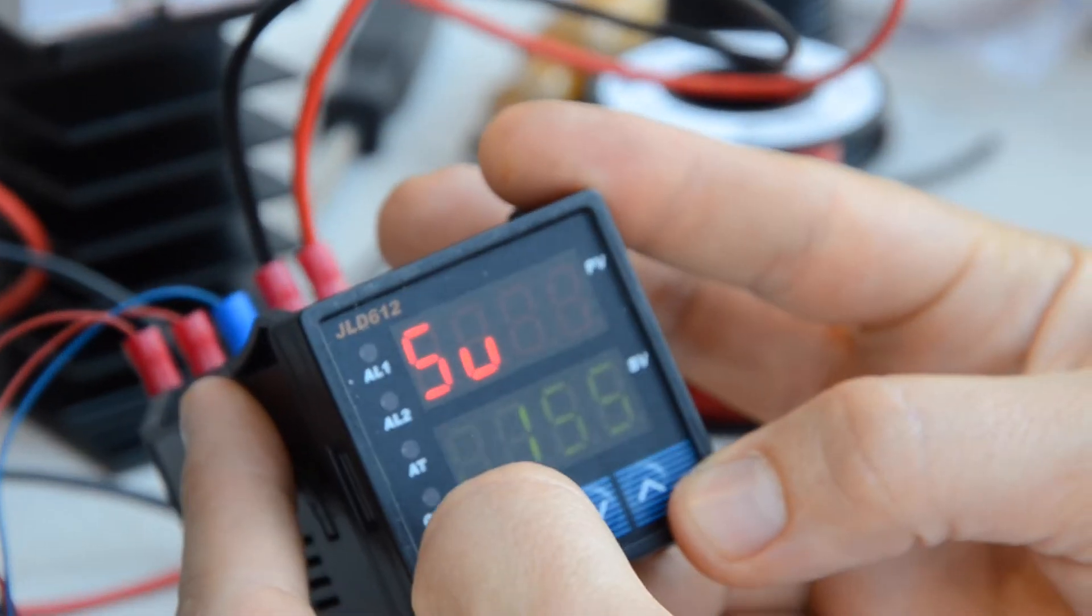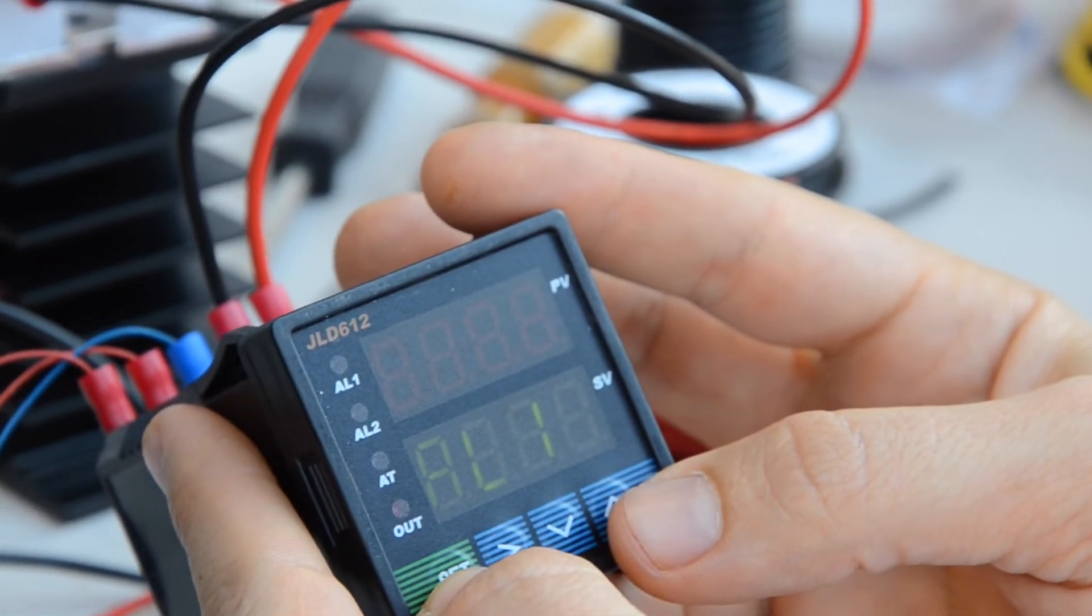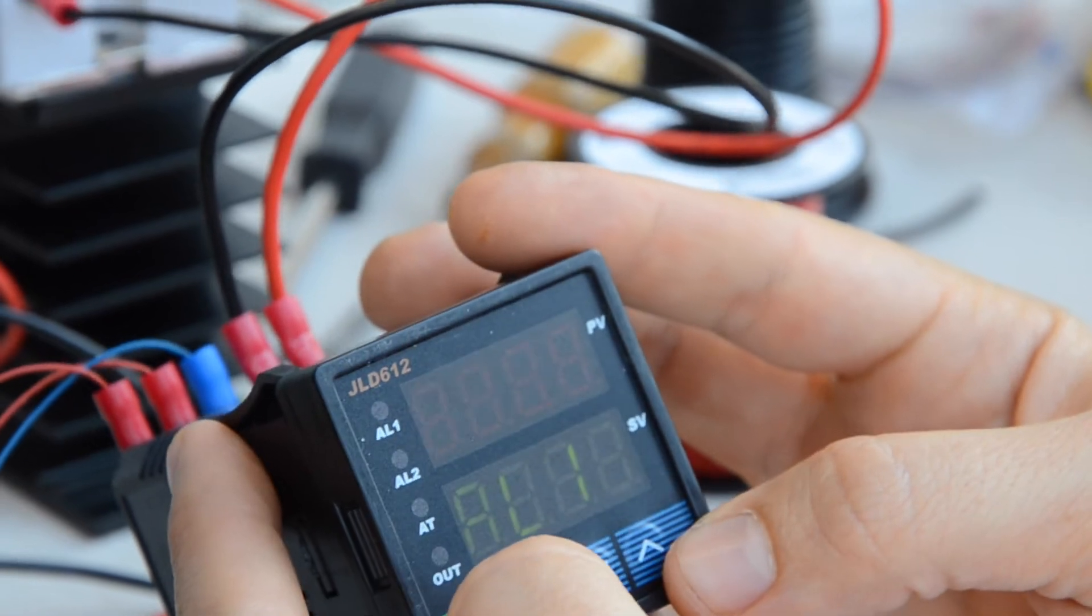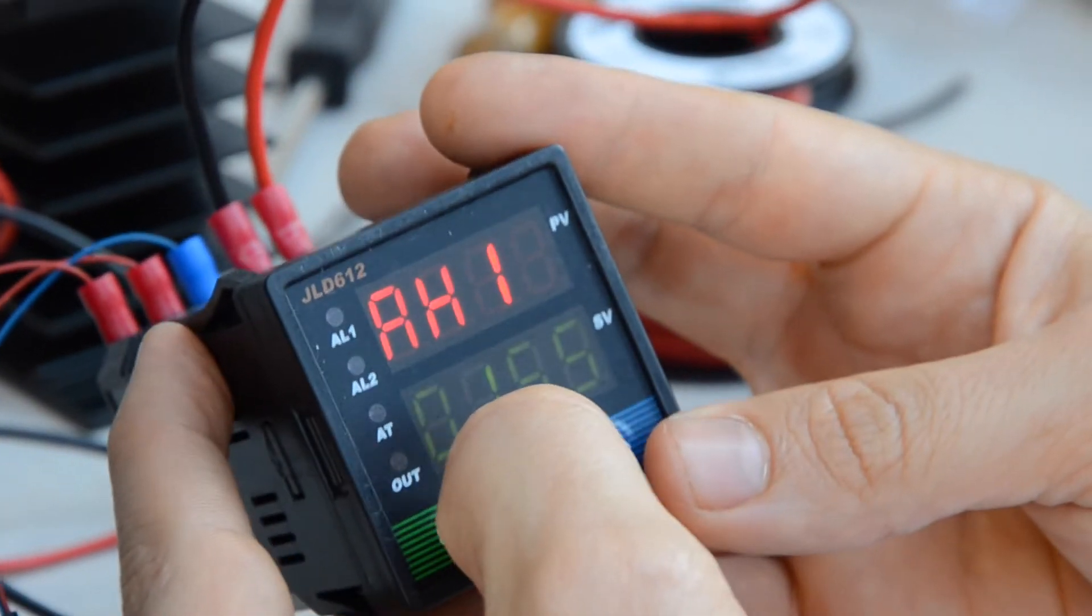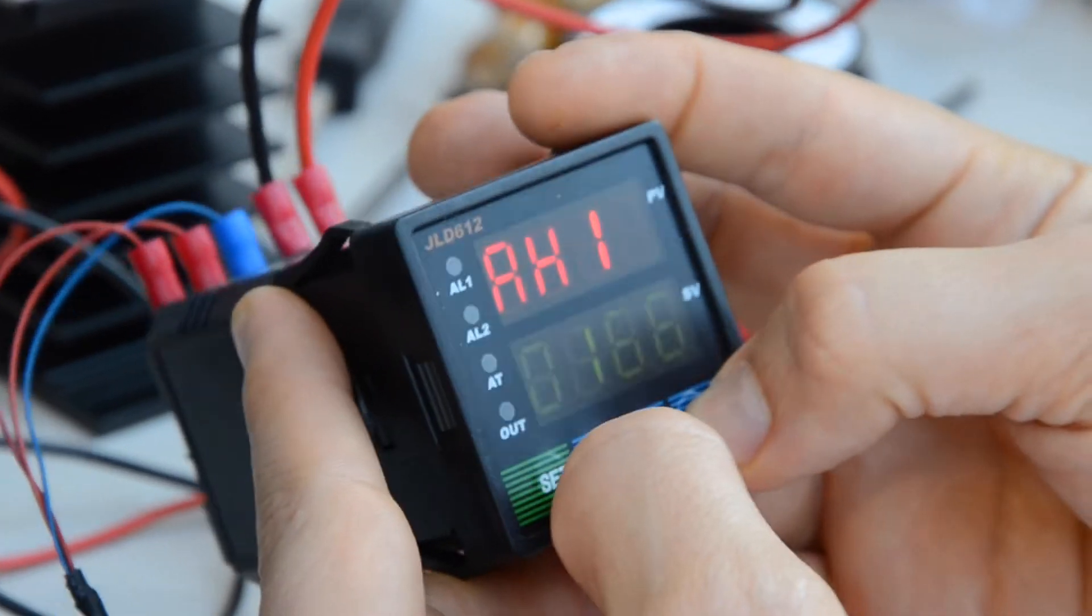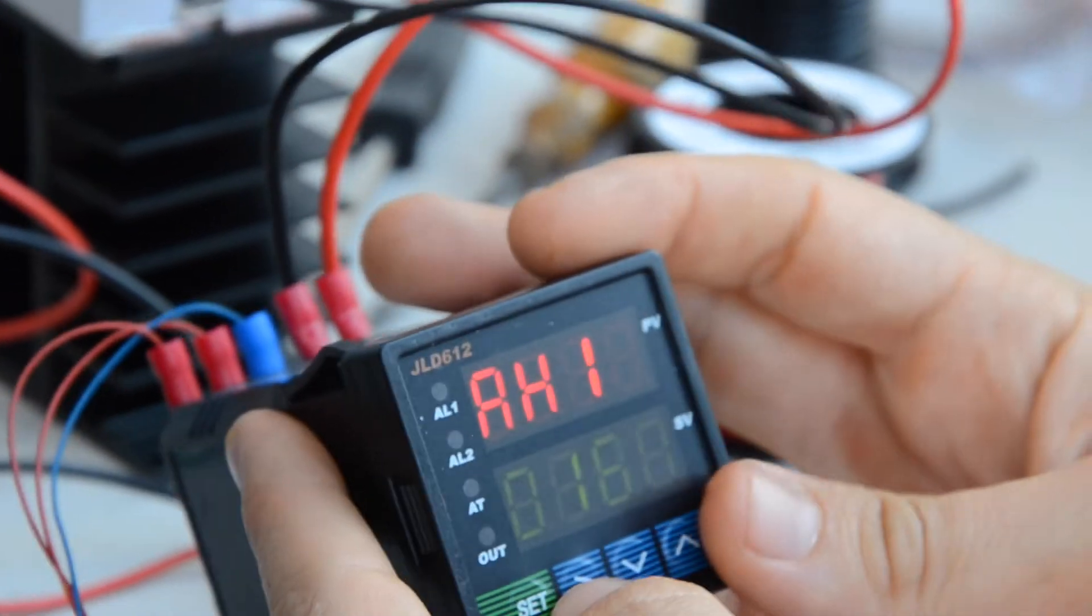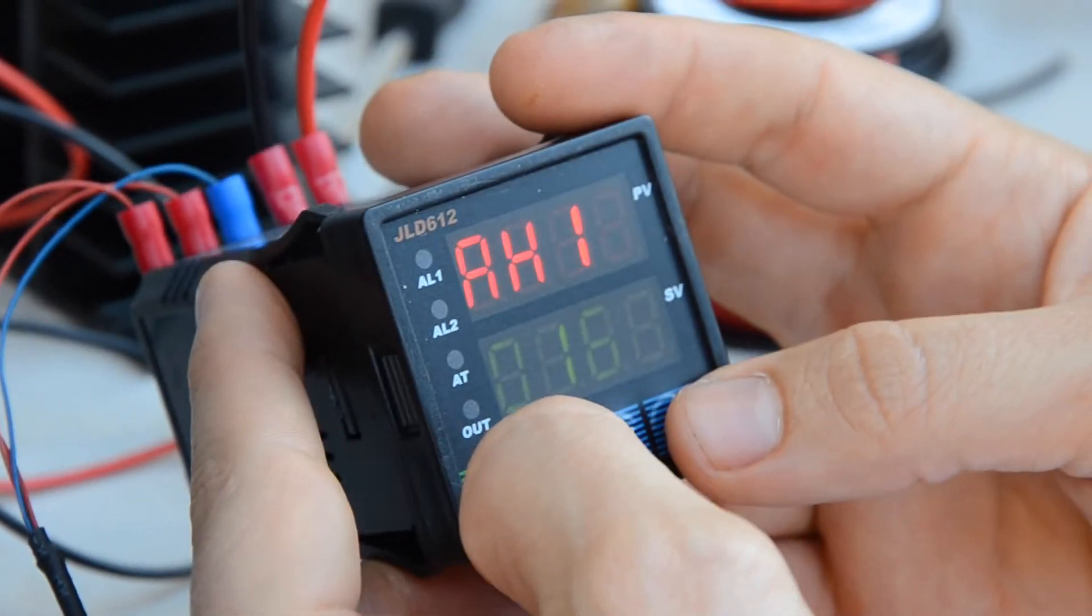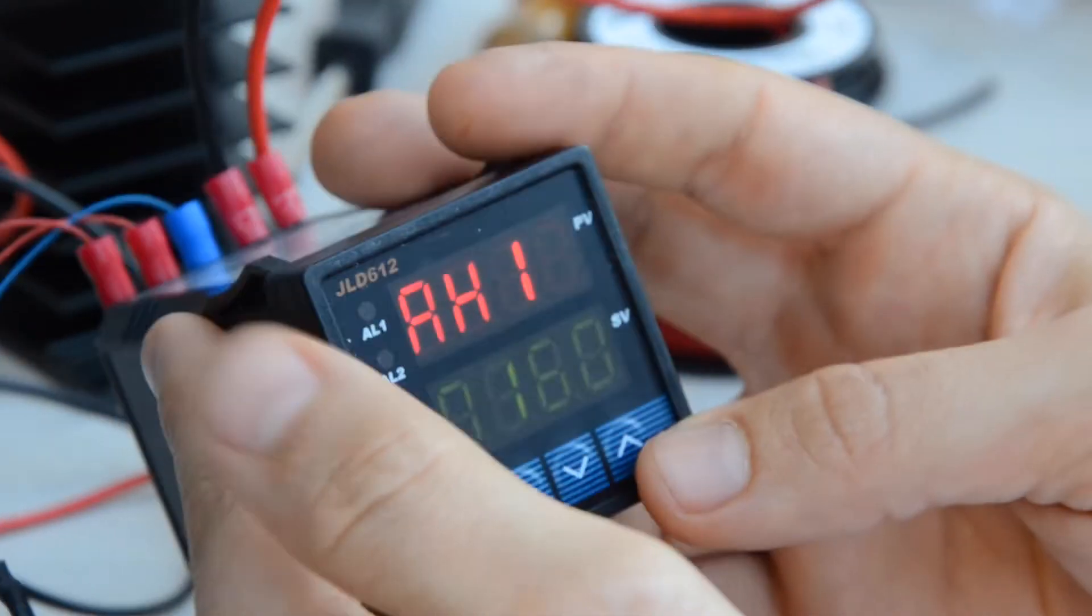It's already set, so I'm going to go ahead and OK that one. Then the next setting we're going to do is the first high alarm. I'm actually going to lower this one down to 160. So that means that if the temperature goes above 160, it'll actually put out a little buzzer alarm, which we may or may not necessarily even need once this thing gets tuned.